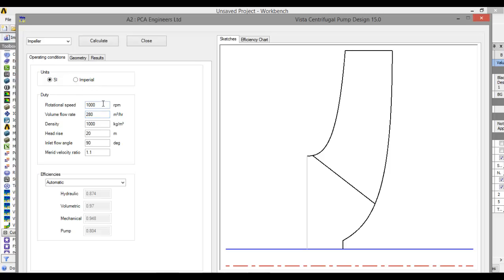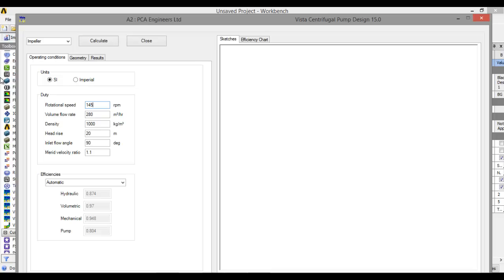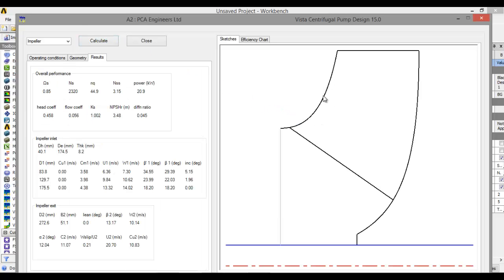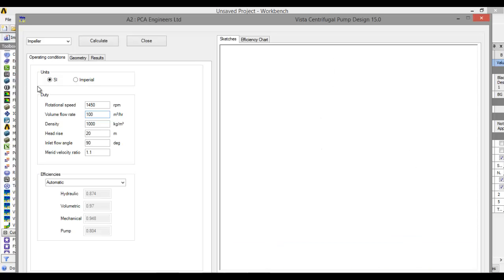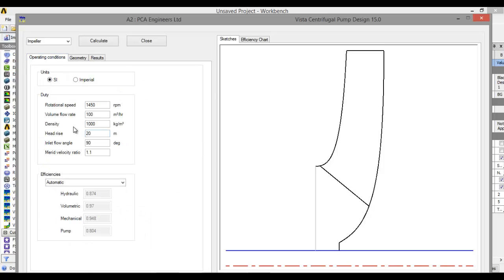Now let's set rotational speed back to 1450 RPM and increase the volume flow rate — let's say 300. Click on Calculate. Here we see that if we increase the volume flow rate, the length of the blade decreases and width increases. Let's decrease the volume flow rate to 100. Click on Calculate. Here we see that if we decrease the volume flow rate, the length of the blade increases and width decreases.